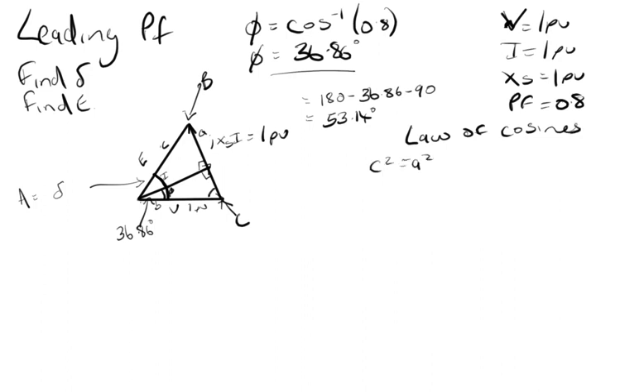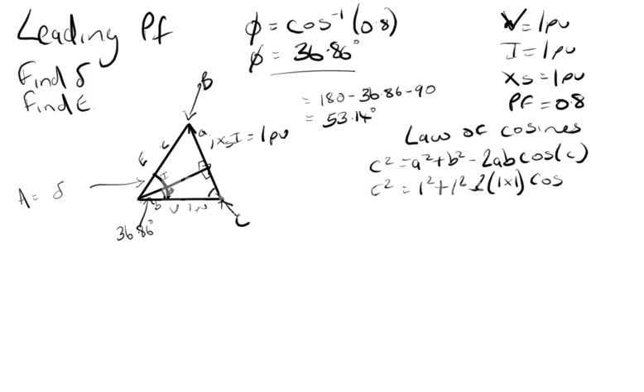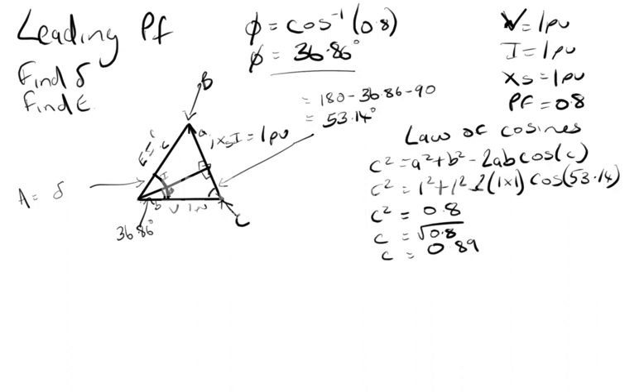We have the hypotenuse c, opposite a, adjacent b, with delta as angle A and angle C = 53.14°. Using the law of cosines: c² = a² + b² − 2ab·cos(C), so c² = 1² + 1² − 2(1)(1)·cos(53.14°) = 0.8. Therefore c = √0.8 = 0.89 pu, so excitation E = 0.89 pu.